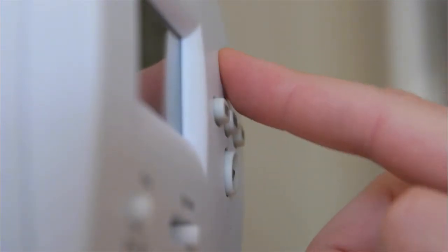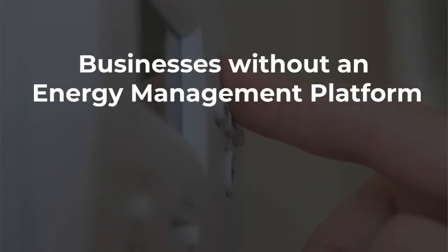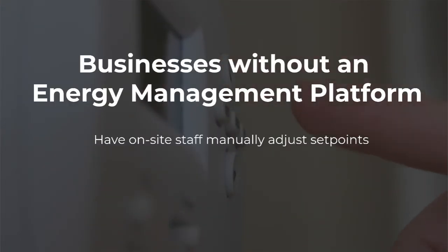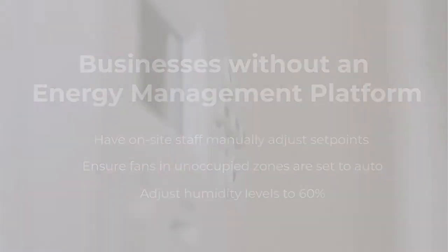If you don't have an EMS system, you can manually update these settings for each zone as needed. Use a programmable thermostat or delegate on-site staff to manually adjust set points to the previously recommended settings for occupied and unoccupied zones. Ensure all fans in unoccupied spaces are on auto and adjust interior humidity controls to allow for 60% humidity.